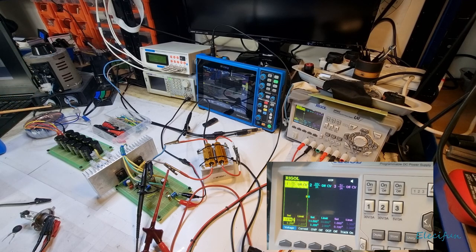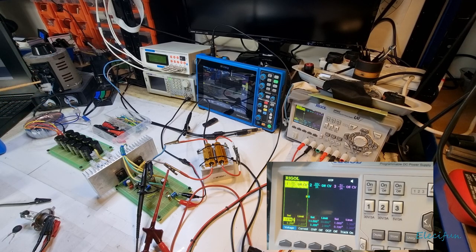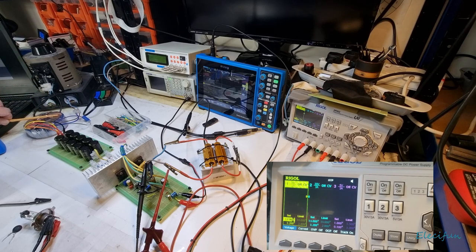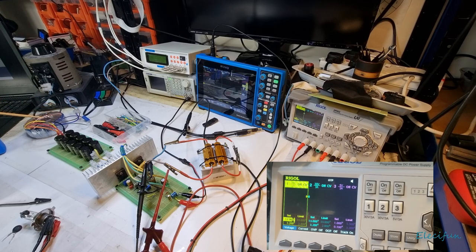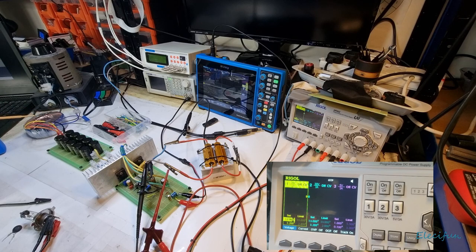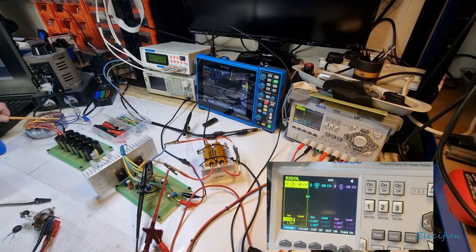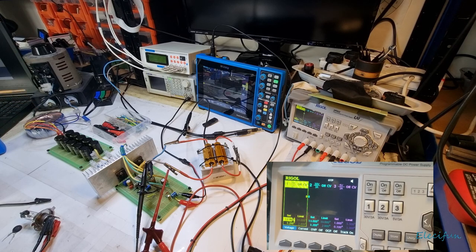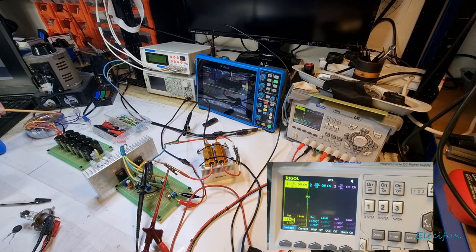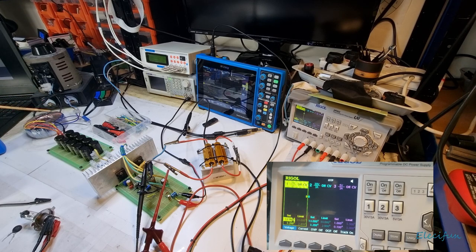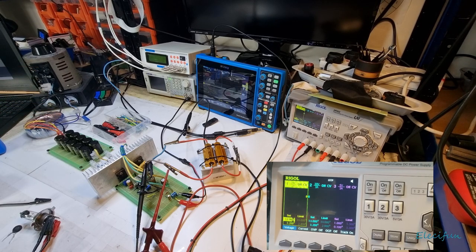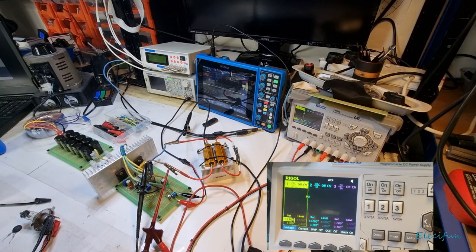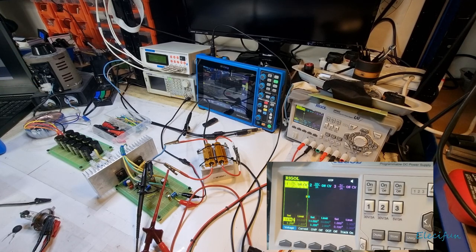Same thing here. Normally I wind this up slowly to prevent that, but if it's just left in that state where it's high voltage, it can do that. And at the same time that can happen here as well, because if this is only rated for three amps and it's pulling let's say five amps through it, it's going to put a lot of tension on these wires, on these turns, and you can end up damaging your transformers.